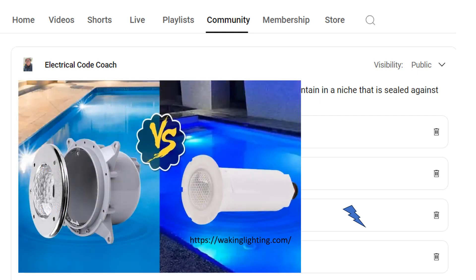This photo was taken from wakinglighting.com — you can go over and check them out. On the left-hand side is a wet niche light, which allows the fixture to be submersed in the water. On the right-hand side is a no-niche light. The one we're talking about today is somewhere in between: it has a niche, but it does not allow the entry of water. It's very important that we understand what light we're installing because the codes will change depending on that.